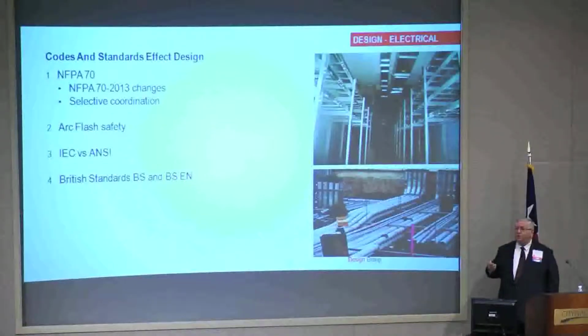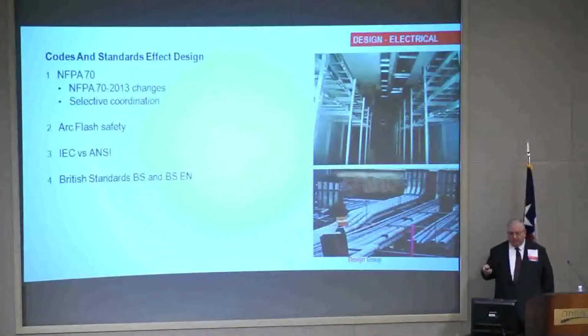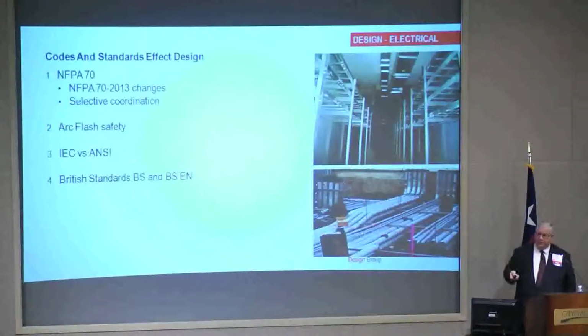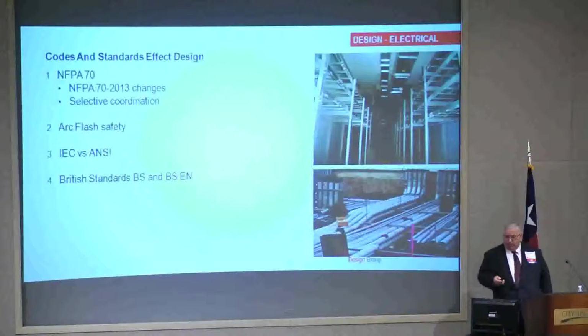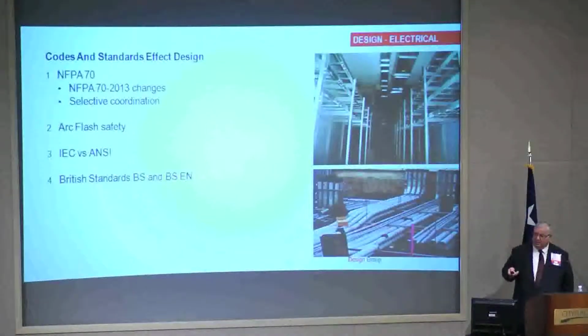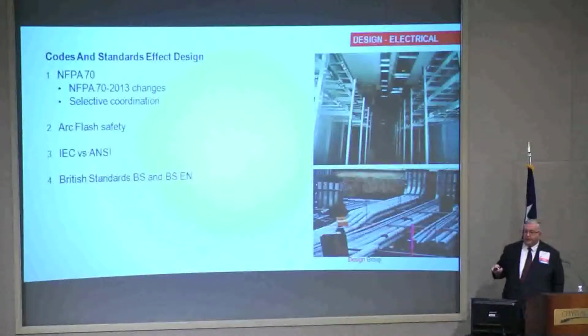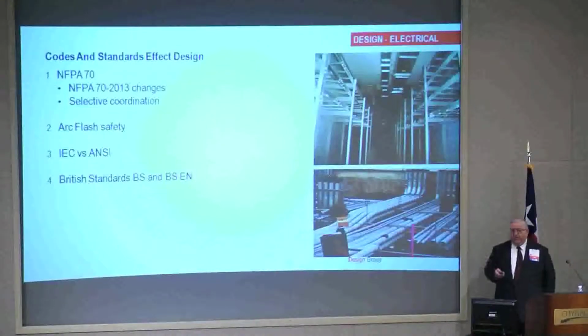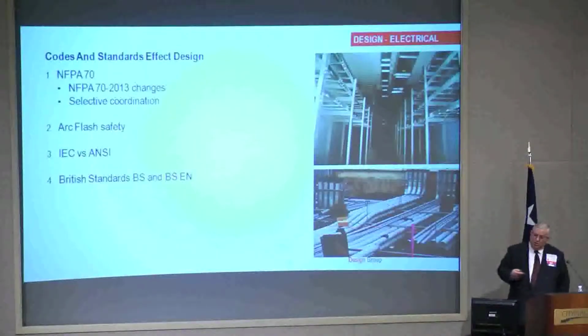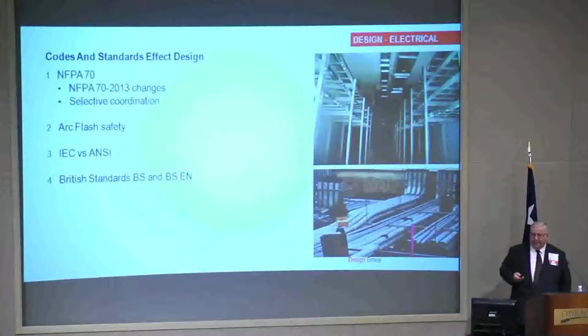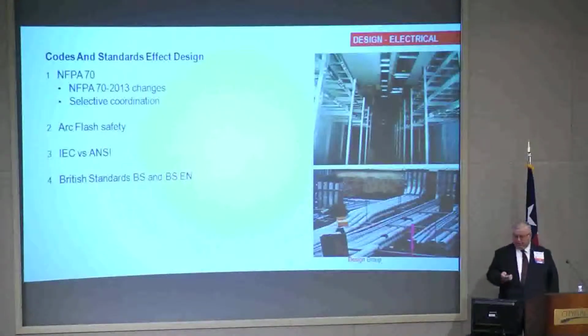NFPA 70 is the National Electrical Code. It's cited by many states and many countries, but it is different than the British standards and how they design. On the right are two pictures. One is a utility tunnel, which is a connection between the generator building and the data center. It's cable trays in a tunnel versus the picture below, which is a typical US design, which would be PVC conduit that's going to get buried in duct banks underground. More cost effective, less of a space issue in a building. But if you follow the British standards and use cable tray, then you end up with building tunnels, and it's a different design philosophy and space requirement as you work.